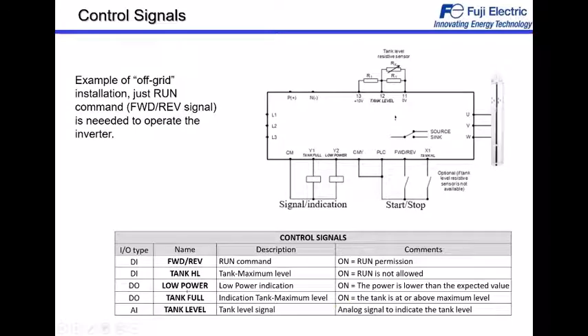There is another alternative, and it's an analog input giving us a sensor, giving us a tank level signal. We may want to stop the tank not at 100%, maybe at 60% or 80%. Maybe the season does not require that we have the tank full, and then we can stop the tank at 60 or 80%. In this case, this analog input is showing the tank level signal, and then we can program at which level we want to stop the system.